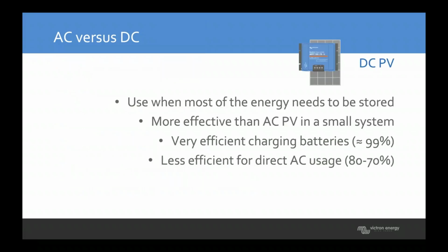Now, DC PV. Use it when most of the energy needs to be stored in the battery. It can be more effective than AC PV in very small systems. We make very, very small MPPTs down to 20 amps, I think it's the smallest one. Maybe there's even a smaller one, 15 amps. There's no Fronius that's that small. So in very, very small systems or systems where there's no AC at all, only DC systems, then a DC PV system makes a lot more sense through a Victron MPPT.